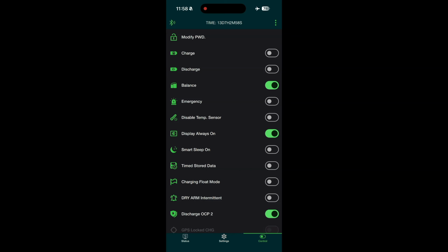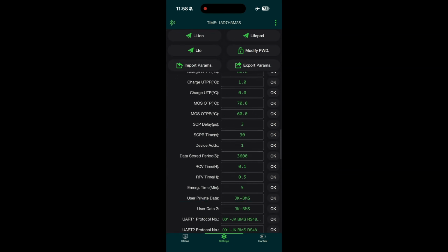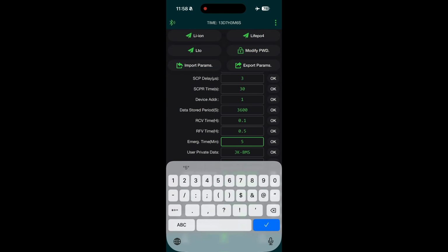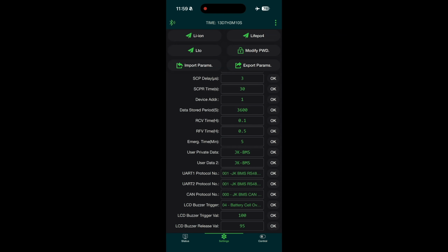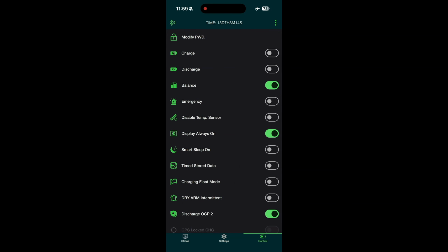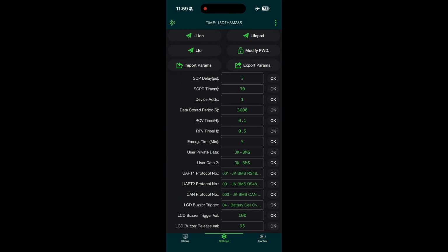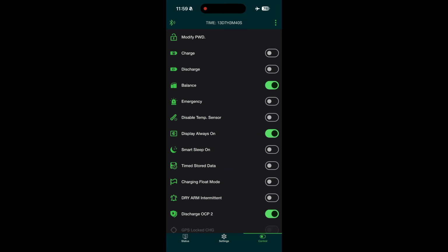Emergency. This is the setting I mentioned before, where we've got the emergency time minutes. If you turn this on, it ignores all the safety parameters you've put in and allows the BMS to accept charge and discharge. It waits for the timer to go to 0, waits 5 minutes, and then turns off this emergency timer. My suggestion is not to use it if you don't have to, since it ignores all the safety parameters and can be potentially dangerous.